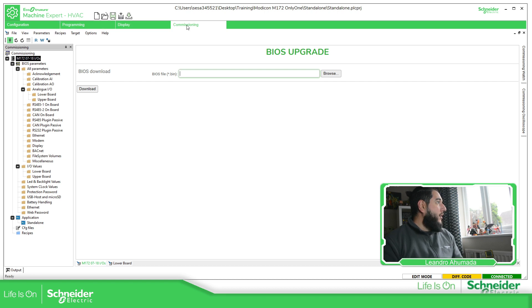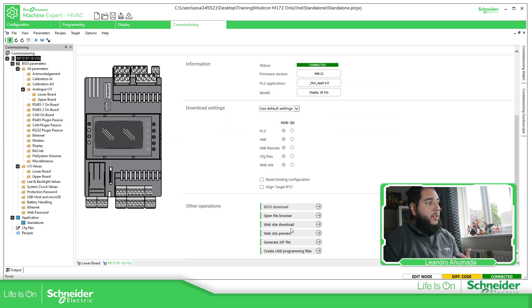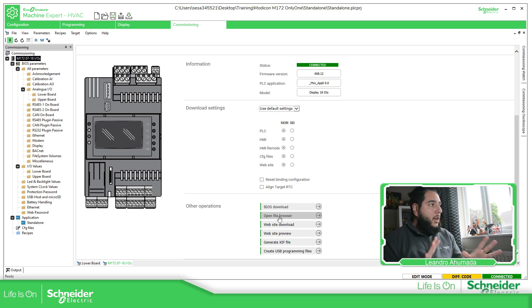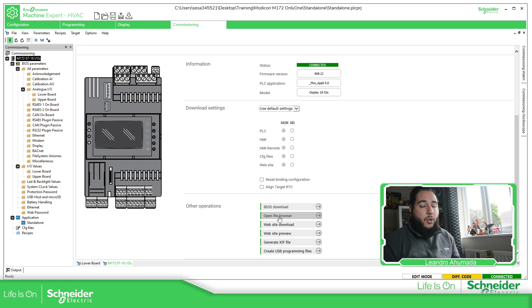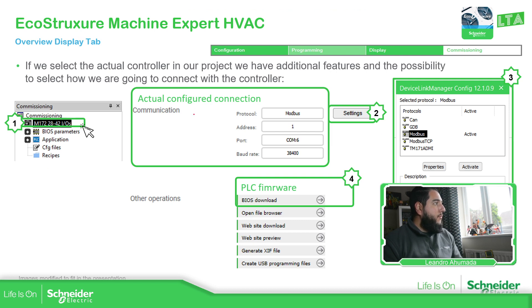You also have the possibility to see and download a website to the controller, which is similar to the visualizations but different. You can generate files for use on a USB stick, and you can also access the PLC's FTP server. There are several useful things inside the commissioning tab — it's very useful if you need to modify the Ethernet, serial, or analog input configuration without having the full application. You can simply connect and make the modification.